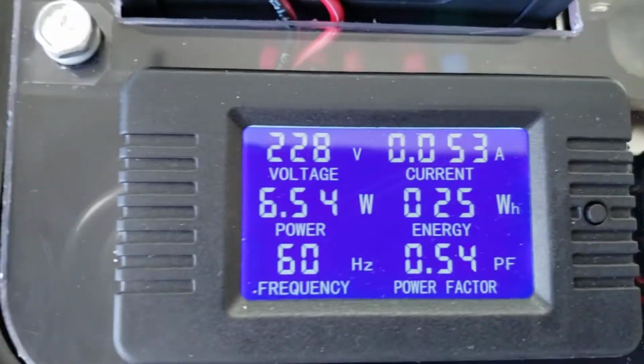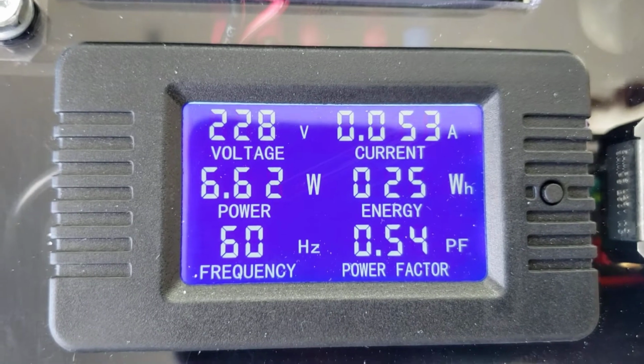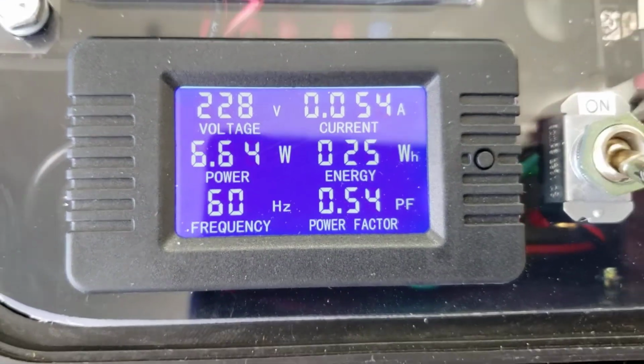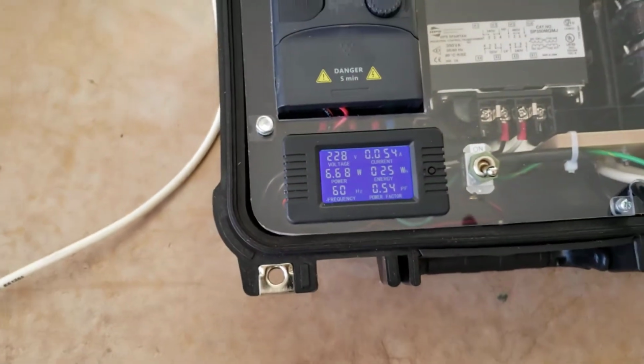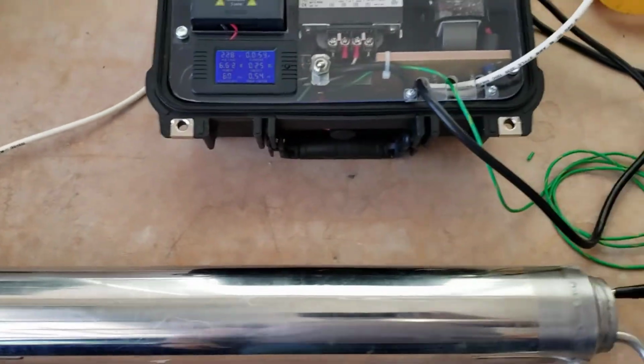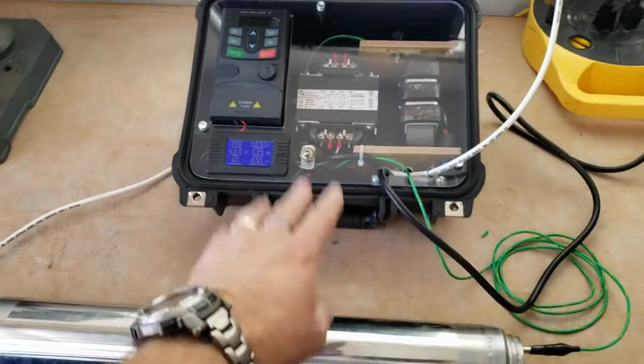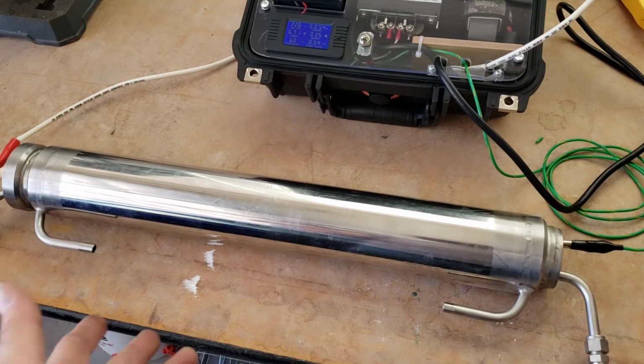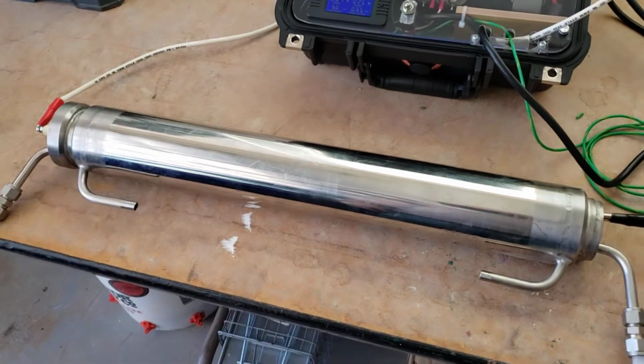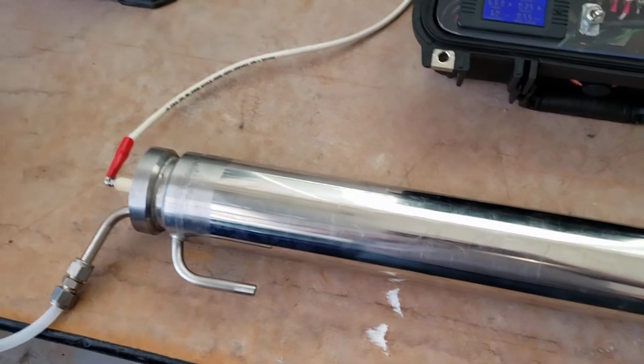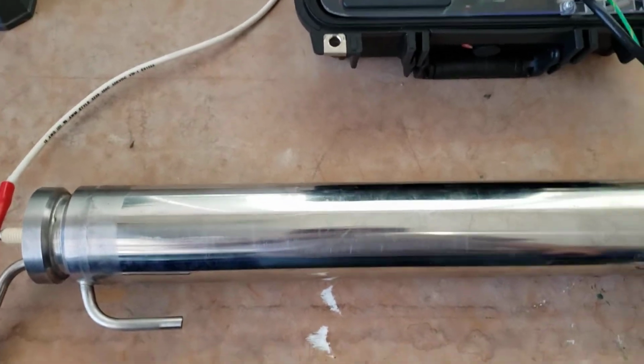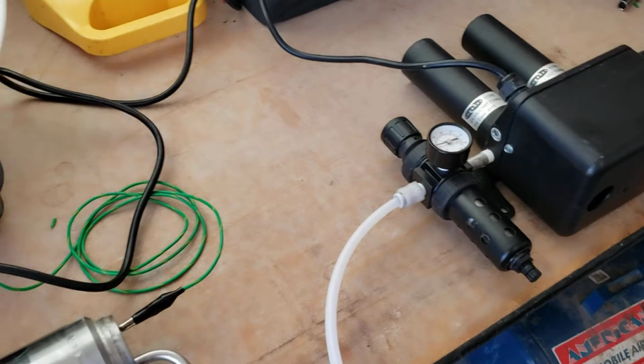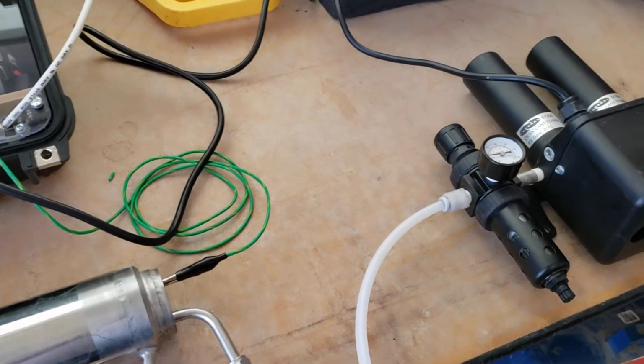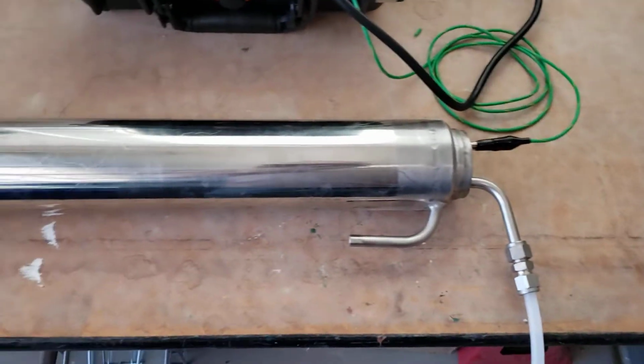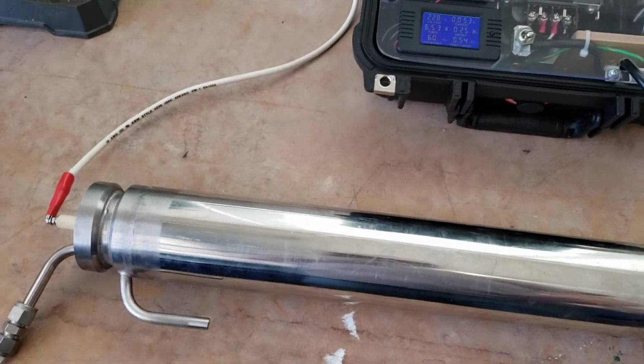On the power meter, you're going to have the voltage and wattage, frequency, current, and all that information. When you're ready to test it, you can turn it on from the cell. Now you can have cooling water or not. It doesn't matter. The tests are generally pretty short, so the cooling water is not that important. But you do need to have it at pressure, and preferably with dry air source or oxygen, whatever your normal feed gas is. If there's high dew point air going through the cell, it could cause it to fail, even if it's not a bad cell.